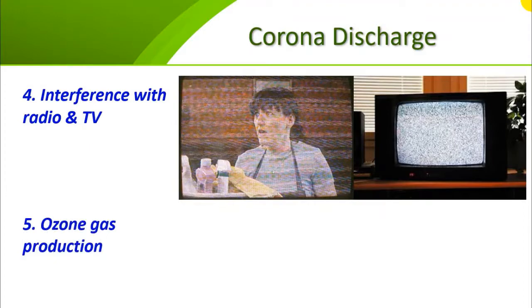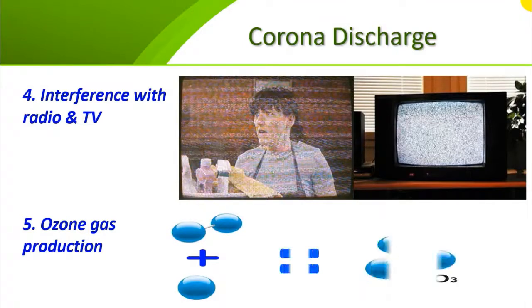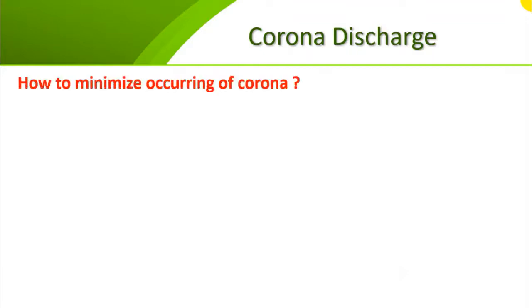Corona also produces ozone gas. Due to the ionization of air, oxygen breaks into two active oxygen ions, which recombine with oxygen molecules, forming what's called ozone gas, O3, which can be smelled. Also, ozone gas can reduce the life of the insulator and conductor. So, from the previous points, you understand that corona formation is not a good thing to happen. So, how can we minimize the occurrence of corona?